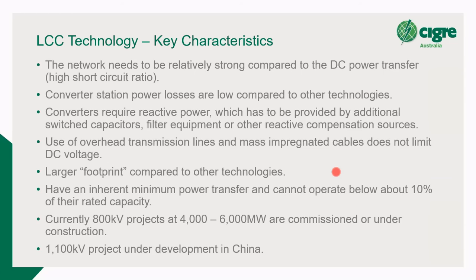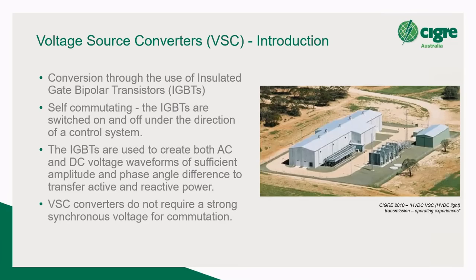There is also this issue with the power electronics, with the thyristors, where there's an inherent minimum power transfer. It's a dead band. Typically, it's 10% of the rated capacity. Although there are some innovations recently, particularly the New Zealand link, they've worked out how to utilise bipole systems to minimise the impact of that dead band. Currently, 800 kV projects, of course, I've just mentioned the 1,100 kV, and they're now up around the 8-9 gigawatt, massive projects. So that's LCC.